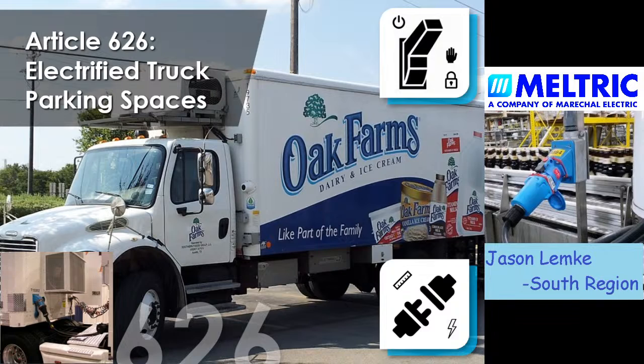If it is fast acting, like say a Type J fuse, we're able to see 65,000 amps through our device while that device trips. We're also able to, in some of our other devices, see up to 100,000 amps before that device trips. Now, having Class J fuses before your plug-in receptacle isn't the most common thing to do. There's a lot of people that will use circuit breakers above your plug-in receptacle for their overcurrent protective device. And when we're doing that, there's a standard closing-on-the-fault rating of 10,000 amps. So all of our devices that are being protected by circuit breakers have a 10,000 amp rating. So I hope that answered the question about how you can close on a fault and whether or not the device stands together.